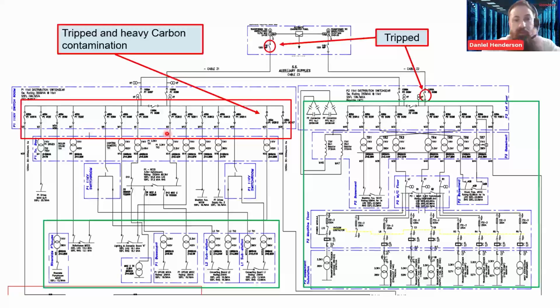switch room, and I've identified that this OCB here has tripped, and there's a heavy amount of carbon contamination behind and at the side of that switchboard. I've then walked further down to that compound that I showed you on the overhead view, where these transformers reside. And these transformers circled green are all fine. I've followed the cables, I've checked the LV boards, and there's no indication there. I've then got to this transformer here, which is the boiler house or powerhouse transformer. And again, there are signs of heavy carbon content on there.